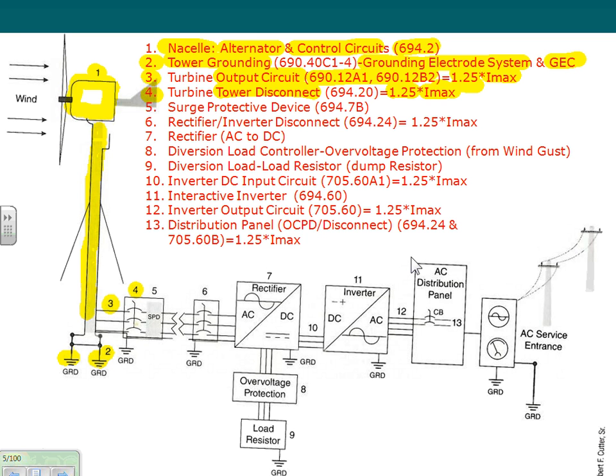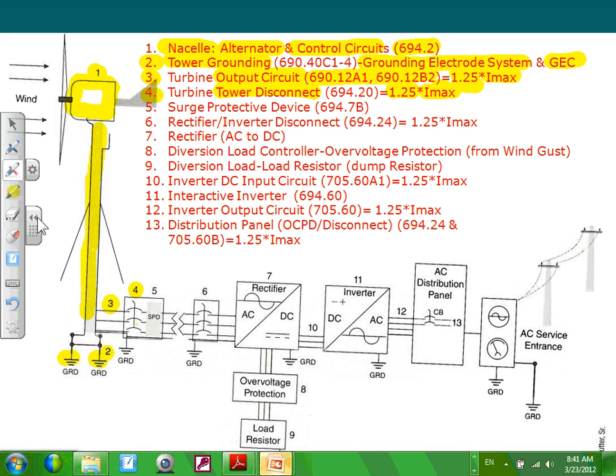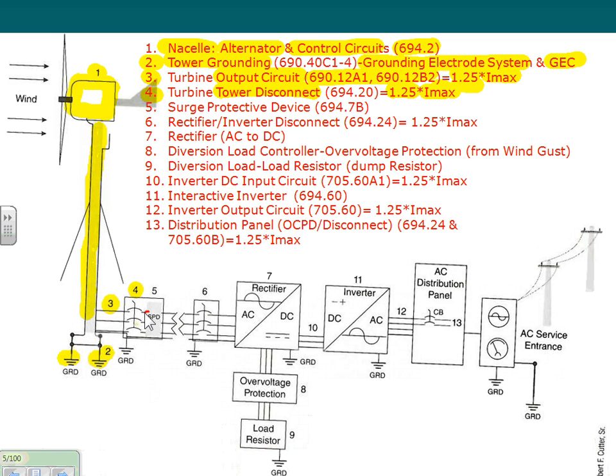So if the speed control of this turbine depends on the output circuit, like we're showing here, if you're taking a feedback wire here, a sensor, sensing the power here and going back to control the speed, so if you see the frequency going out of whack, you slow down and adjust the system. If that's your way of controlling the speed of this turbine, then they don't want you to disconnect the output circuit, because it screws up the control system for this turbine. So that was really interesting.